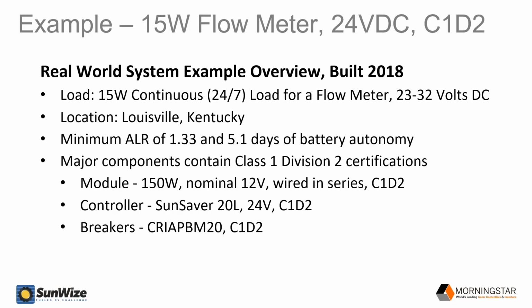One thing I want to point out on this slide is that for the purposes of today's discussion, and in the vast majority of the HAZLOC or C1D2 applications that SunWize services, we're usually talking about a system or an assembly with Class 1 Division 2 components. That is different than a system or assembly that is Class 1 Division 2 certified at the system assembly level. Both of those things exist and are applicable, but primarily we're going to be talking about a series of components whereby the major components have this Class 1 Division 2 certification, and that's often the design solution that we actually see out in the field, not a C1D2 certified system.